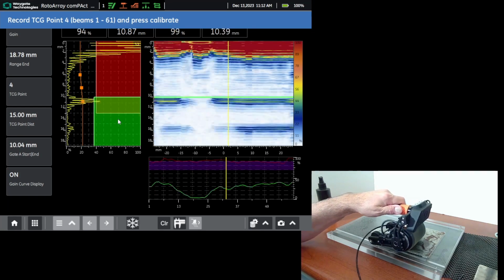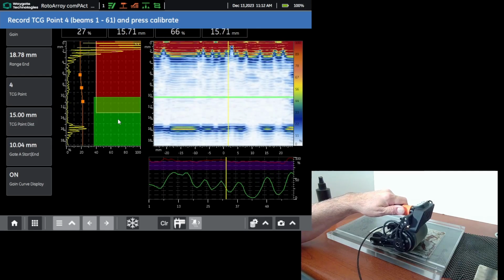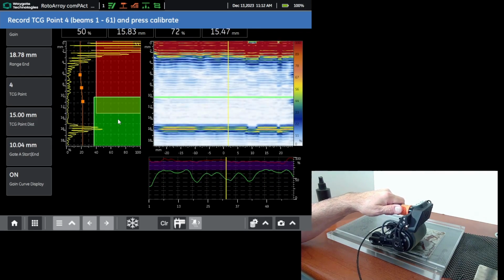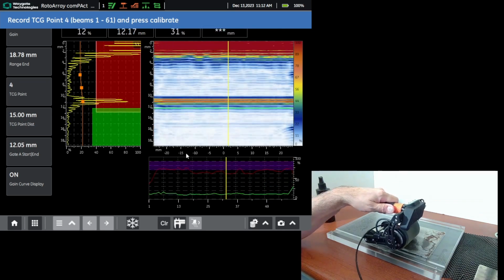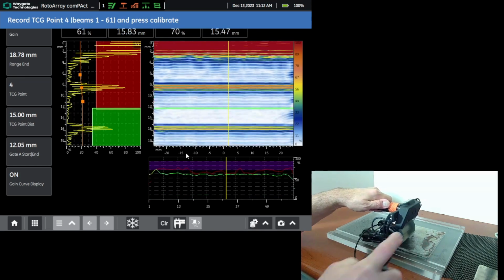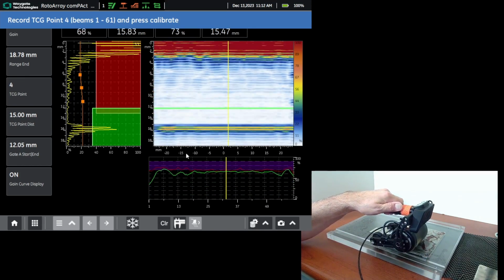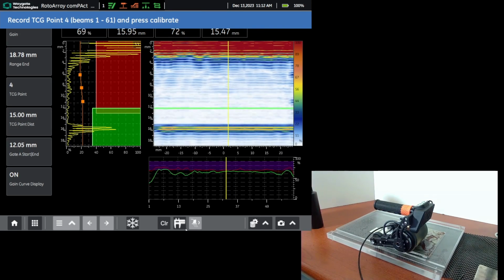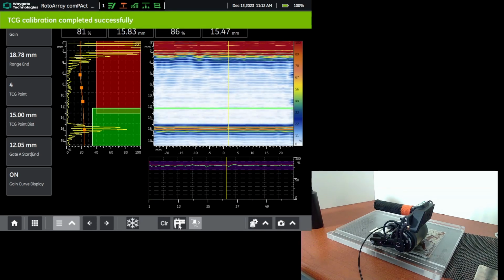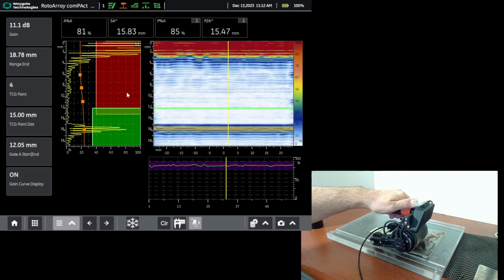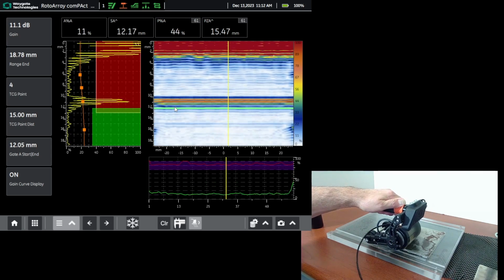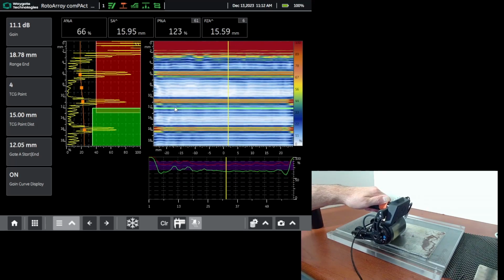It's moved the gate out to get my 15 millimeter step. Okay. Need a little bit more couplant. There we go. Much more even 15 millimeter step. And calibrate one last time. So we have point 4 recorded. We've gotten all 4 points for our TCG. And now each one of those steps should appear at the same amplitude, same 80%. So there's 15, there's 10, 7.5, and 5.